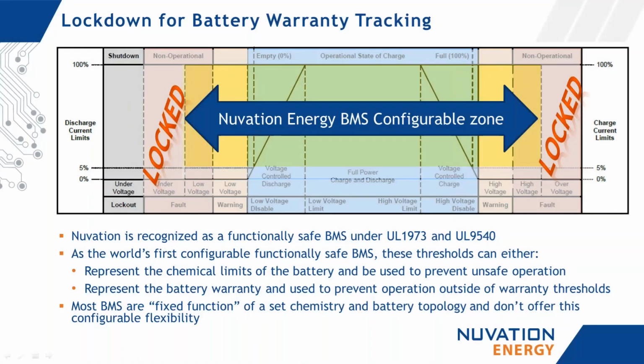Nuvation's BMS is a functionally safe, recognized BMS under UL 1973 and UL 9540. Within that, we have lockdown zones that get locked down in the process and can't be unlocked, as to what the operating limits are for voltage, temperature, and current. Because it's configurable, you can pick that those lockdown points represent the chemical limits of the battery, thereby preventing unsafe operation.